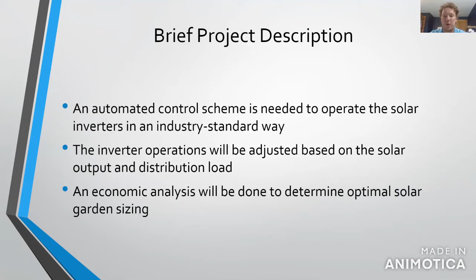This project designs a control scheme for a behind-the-meter solar garden to operate according to industry regulations. This control scheme reads the load on the distribution system and compares it to the output of the solar garden. When the output approaches the load value, it controls the inverter to curtail its output. An economic analysis was conducted to determine the most optimal sizing of the solar garden for a particular member.